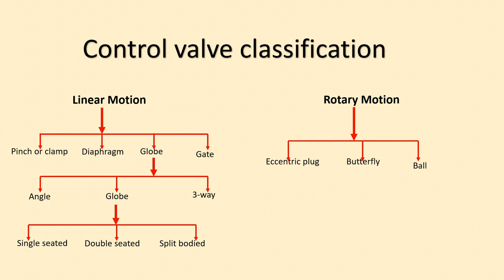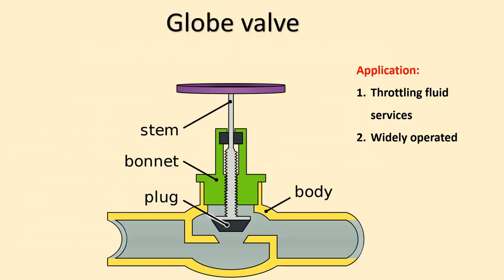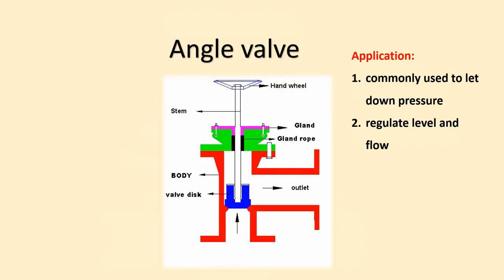This is basically a globe control valve. In an earlier video we discussed the internal components of a globe type control valve body. The main application of this valve body is that it is best suited for throttling fluid service — whether you want a very small, medium, or high flow range, or to control flow, pressure, or temperature. The globe type valve is the best suited type and is widely used in all process industries and applications.